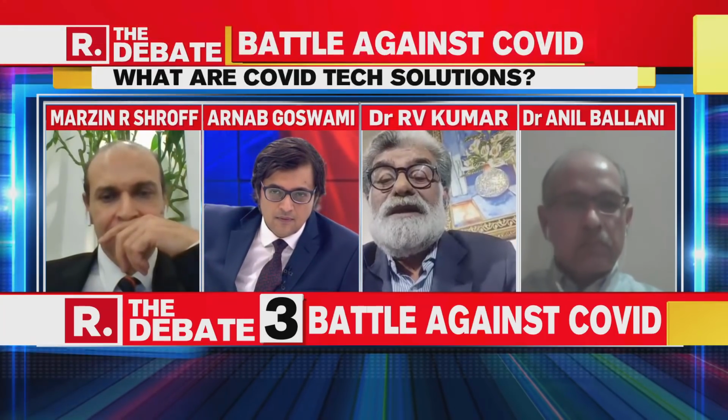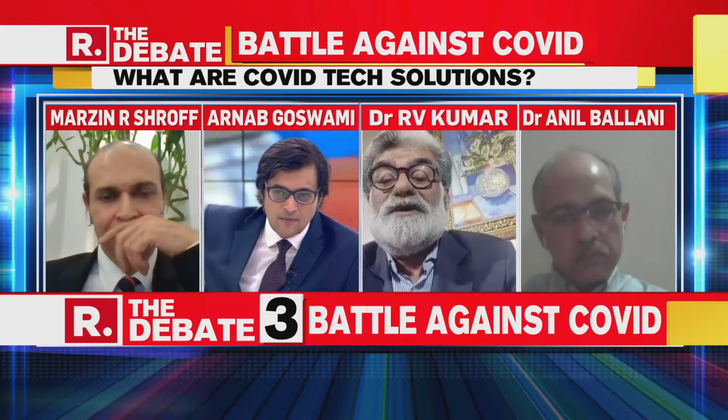You will need 5 devices. Each device would take care of 1,000 square feet of free area. So you may need 5 devices to protect your studio.